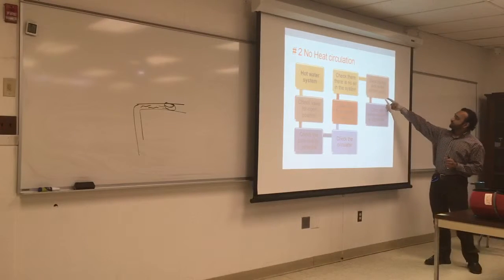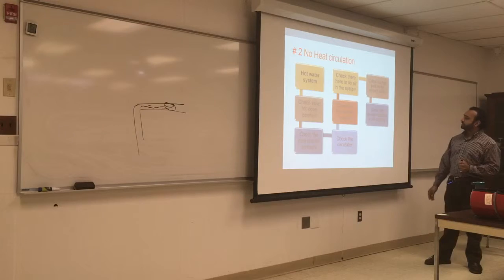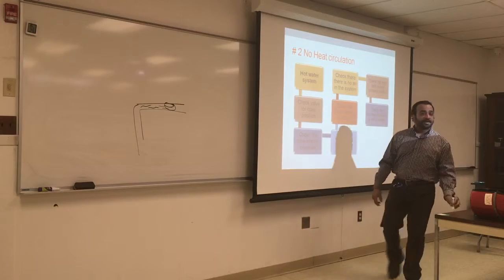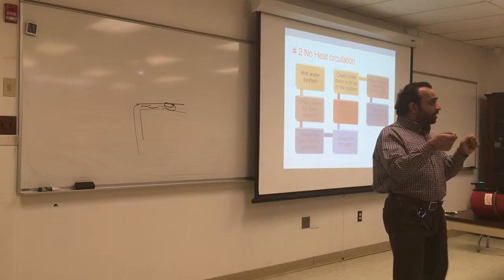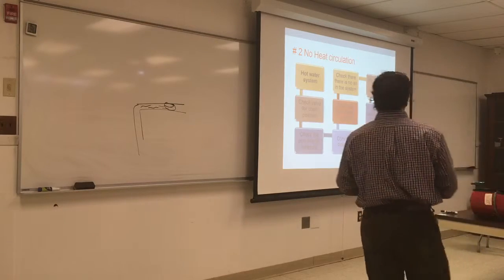Check the high limit on the primary control. Check the reverse aquastat. Check it properly. If the aquastat doesn't get the water between the high and low, it's not going to turn on the circulator. Also check for that.